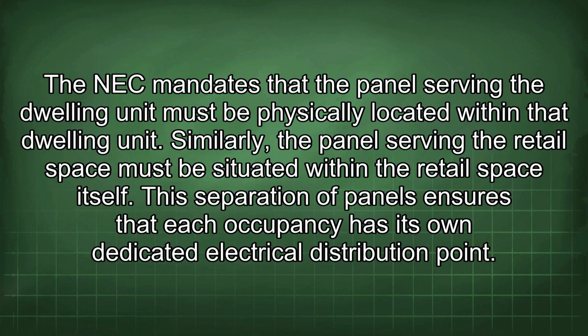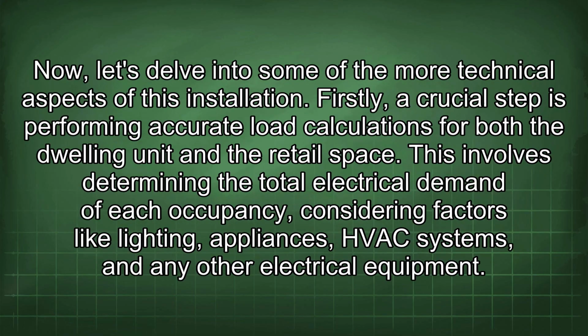The NEC mandates that the panel serving the dwelling unit must be physically located within the dwelling unit. Similarly, the panel serving the retail space must be situated within the retail space itself. This separation of panels ensures that each occupancy has its own dedicated electrical distribution point. Now let's delve into some of the more technical aspects of this installation.